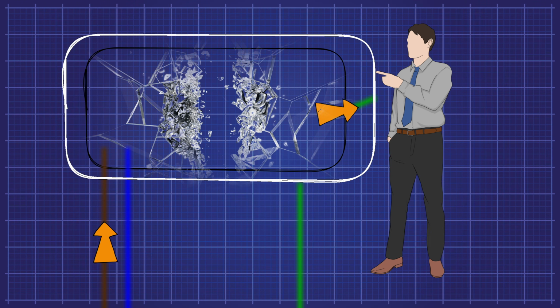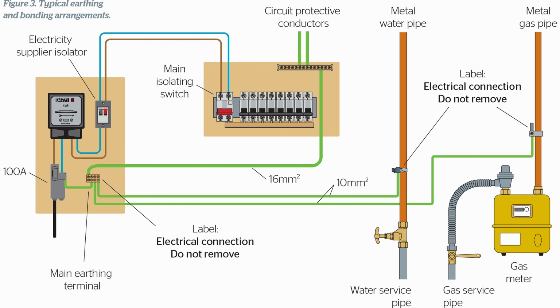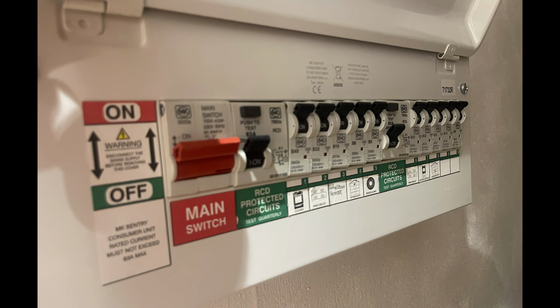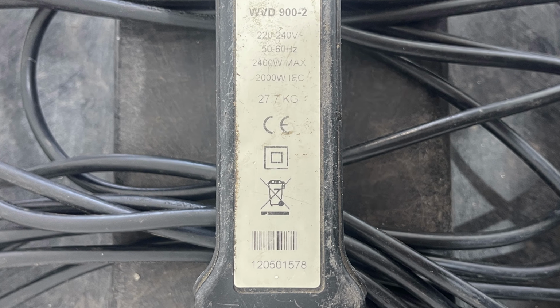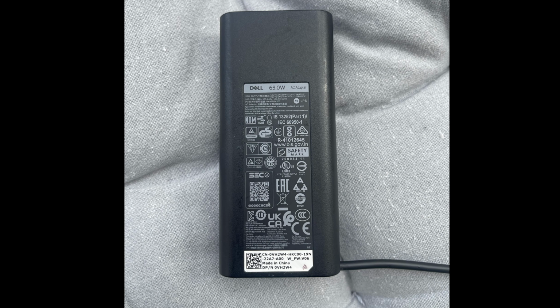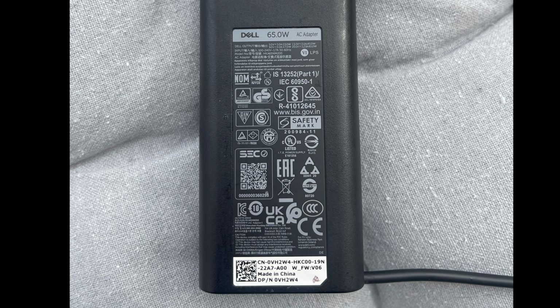In most cases, we want an earth path to detect and interrupt fault currents to protect the circuit from overloading or short circuit. This is what we call fault protection. Fault protection is covered in Part 4 of BS 7671. How is this achieved? We start off by having our protective equipotential bonding to our gas and water pipes and automatic disconnection of supply, such as breakers or fuses. We also have Class 2 equipment, which are fully isolated with double insulation. We might have electrical separation, like we talked about before with our isolation transformer, or we could have SELV, a low enough voltage that would not harm human life. And these are just a few methods of fault protection.